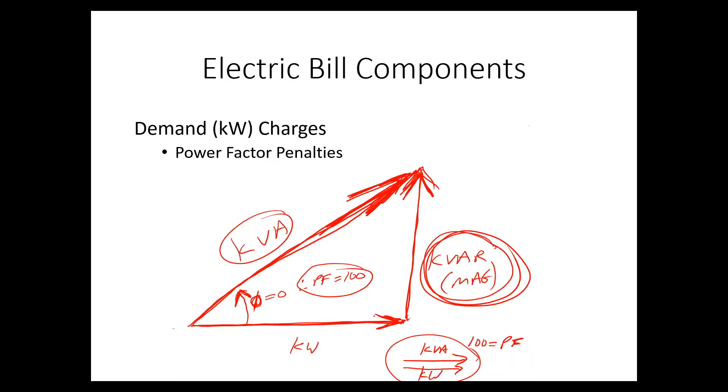The game with power factor penalties is to maximize your power factor, or at least get it to a level where the utility won't penalize you. If the power factor goes below 80% in most utilities, if this angle is such that the power factor is less than 80, most utilities are going to bill you a special power factor charge. We want to avoid that.